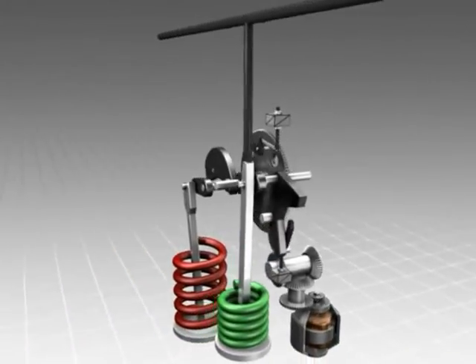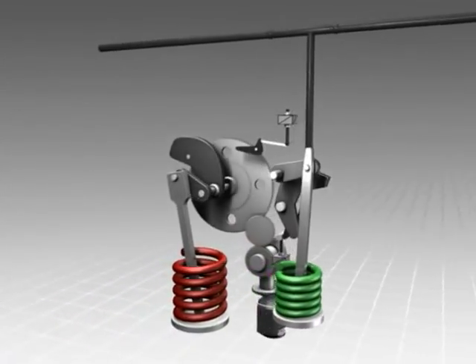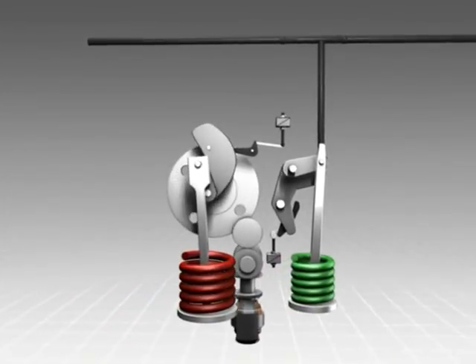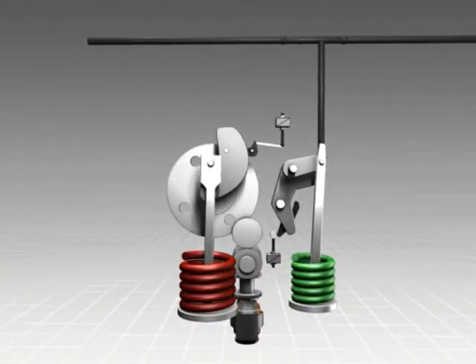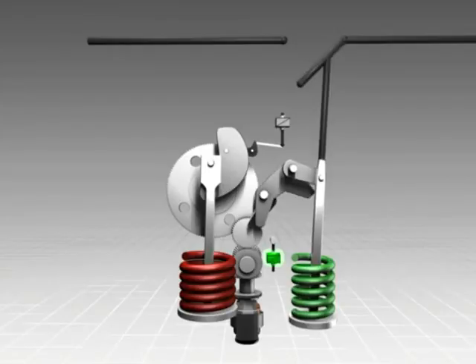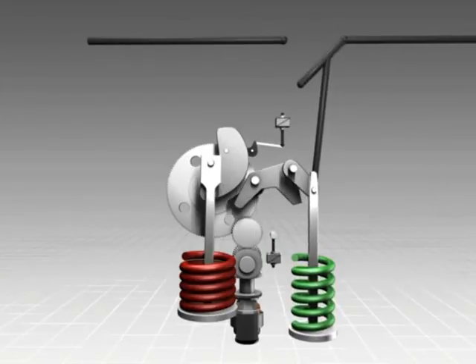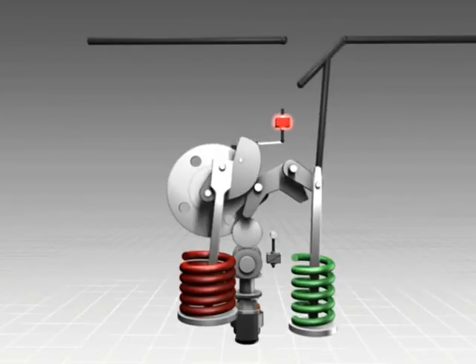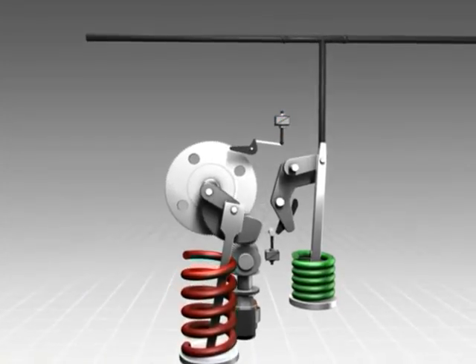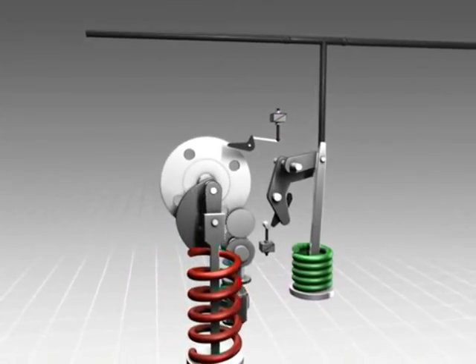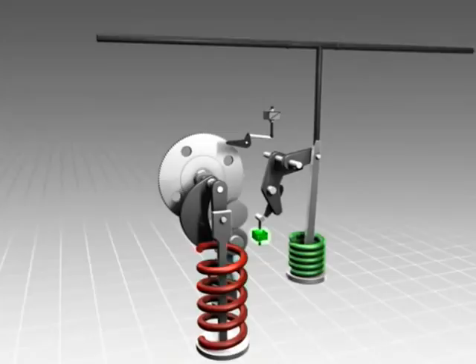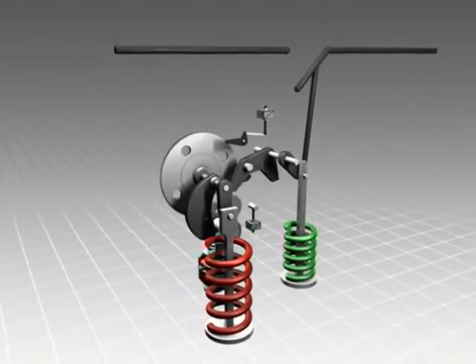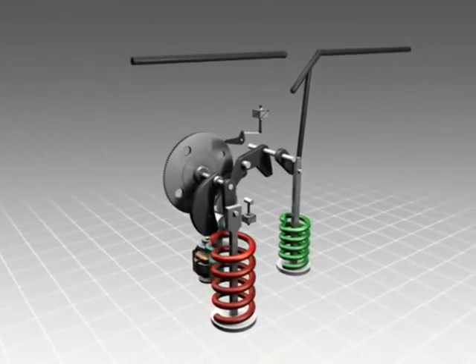The mechanism is built upon well-proven design principles, which include vibration-free latches and load-free decoupling of the charging mechanism. The spring-operated mechanism, which is charged by a motor, allows for a defined switching position that is maintained even if the auxiliary power supply fails. Tripping is possible irrespective of the status of the closing spring.